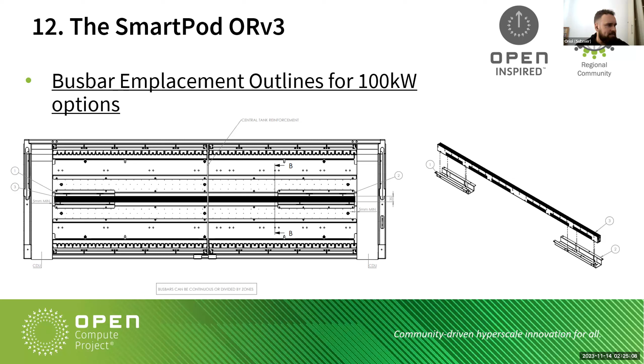This is how the busbar is placed. This is a view from the top of the tank, and this would be the bottom, with the busbar in the center. We can host one busbar or three busbars to have more redundancy or to distribute the density of the power in our tank. This is a 100 kilowatt busbar, but it can also be placed as three on the corners, as you will see.